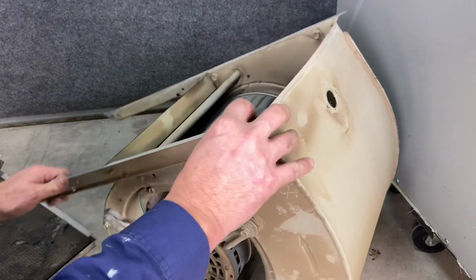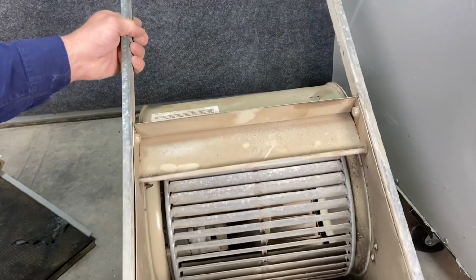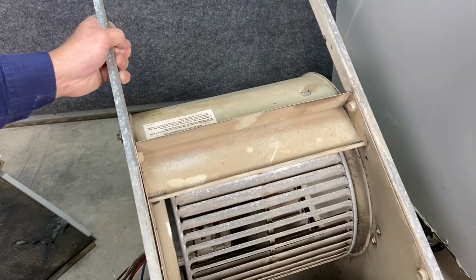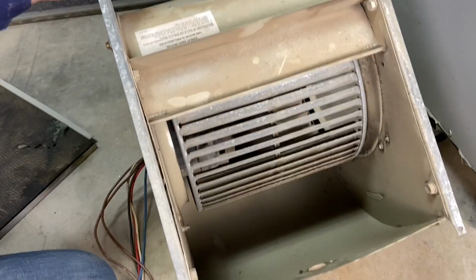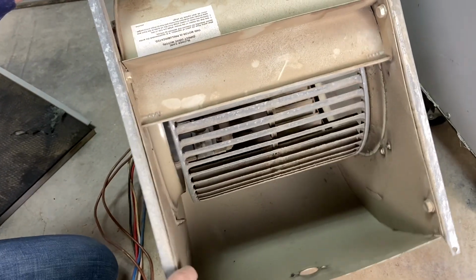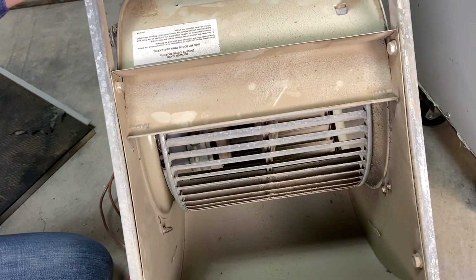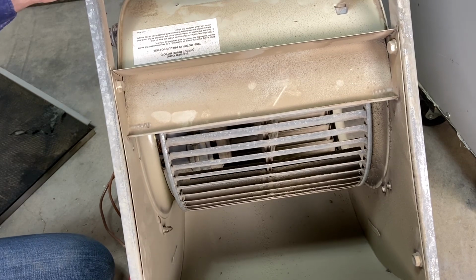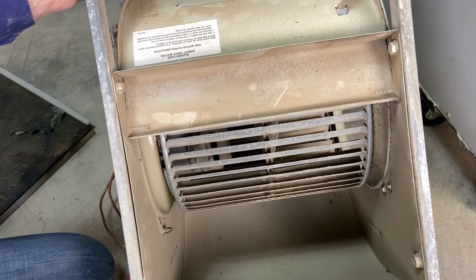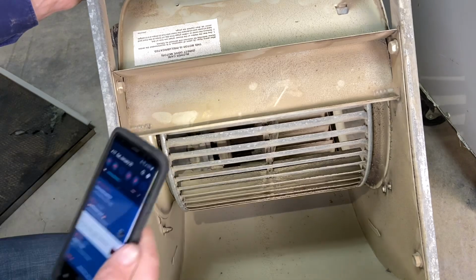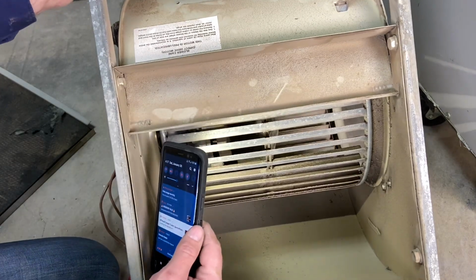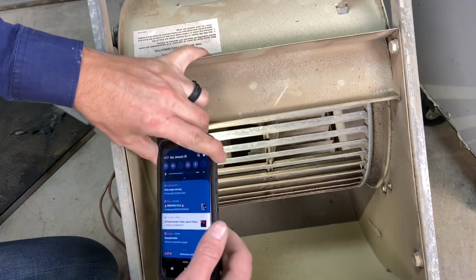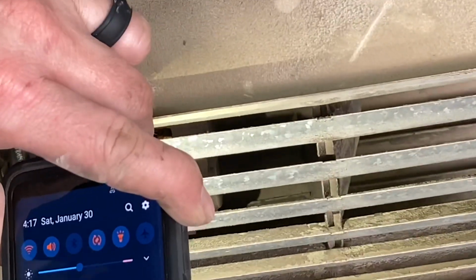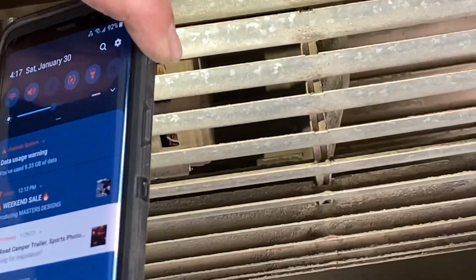If we take a look at the fan for this furnace, there's a significant amount of dirt built up in this blower wheel. And that just happens over time, with the age of the system, but this unit probably hasn't been maintained or serviced very well, or it's in a very difficult location to pull the blower out. If it's in a bad location, nobody wants to pull the blower out of the attic and take it down and clean it. But in this case, there's a significant amount of dirt inside of these blower wheels. We'll zoom in, see if you can see that.